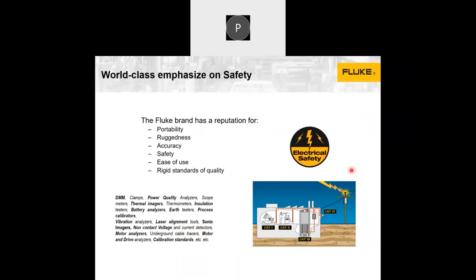Safety is very important for you and us, because if you are playing with voltage and current, it can take your life. When you do these measurements, the only thing between you and the dangerous voltages or currents is your multimeter and its leads. That's why every instrument we manufacture is designed according to the IEC 61010 safety standard, manufactured as per that same standard, and then tested for compliance with external laboratories like UL or TUV. Only after we get that certificate does it come to the market.